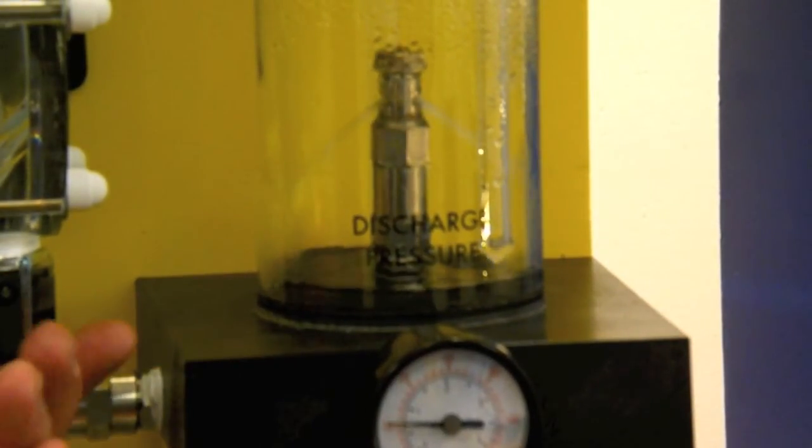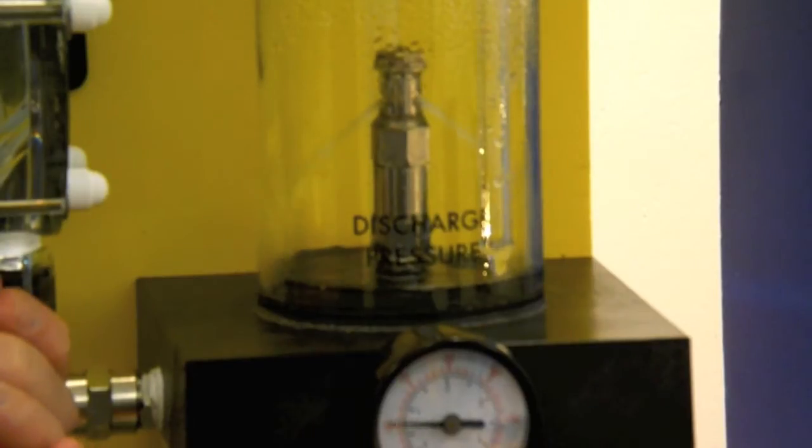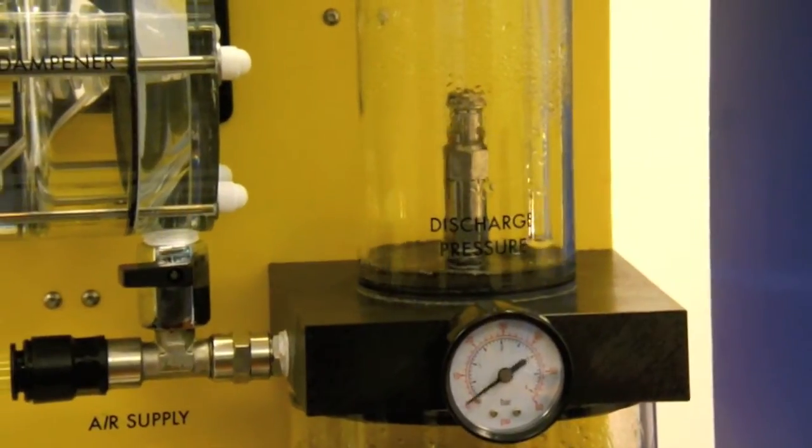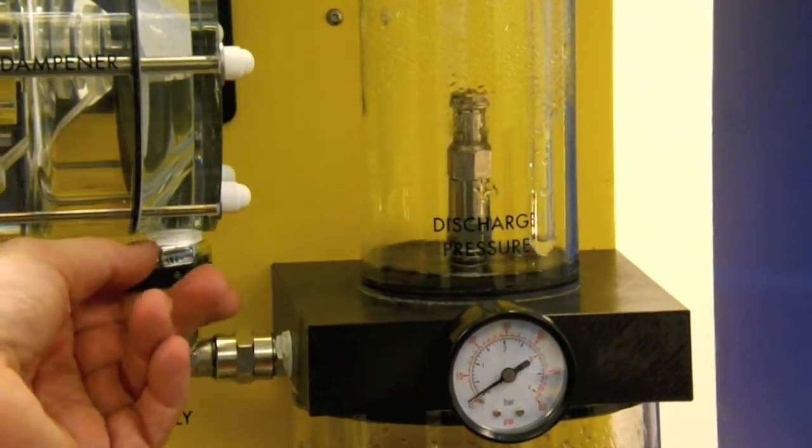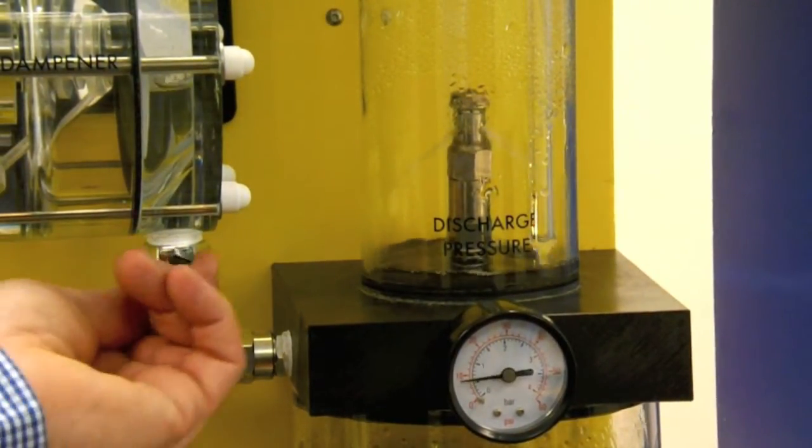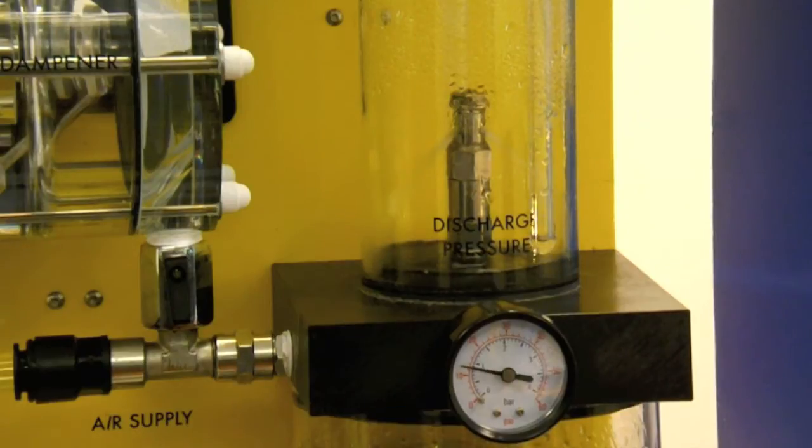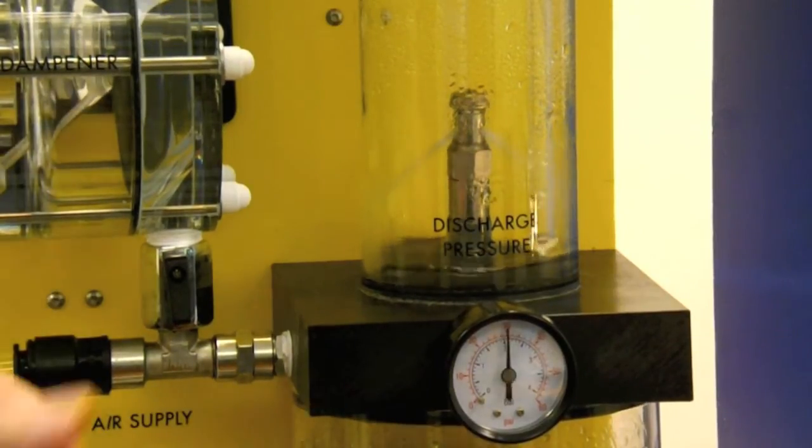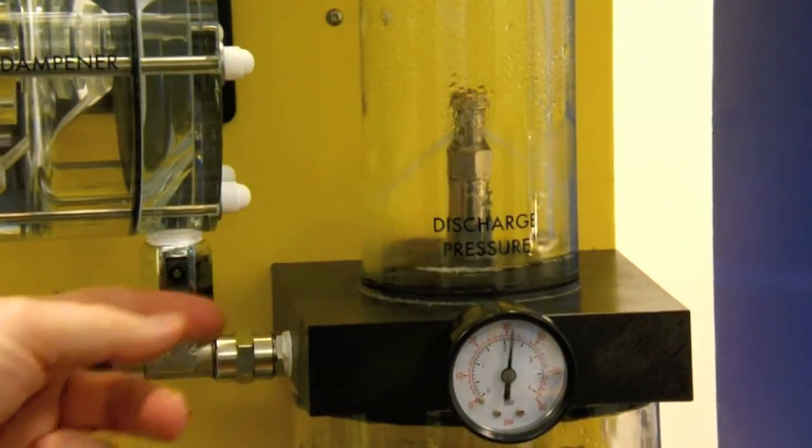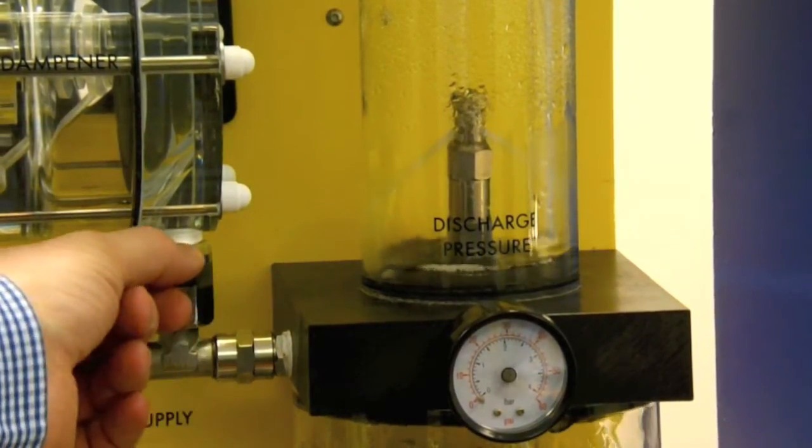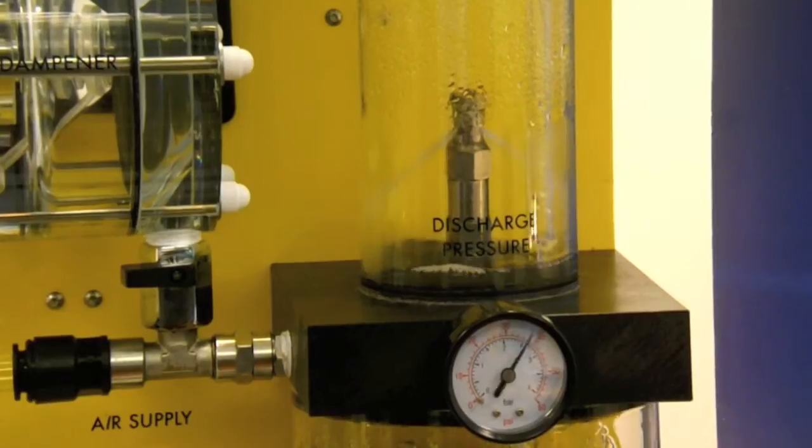So if I close the valve and isolate the damper you will see our pulsation comes back. And if I open up the valve and put the damper back on line our pulse disappears. And this is the same even if we have the pump running quicker. You can see with the pulsation damper on we have a nice smooth flow. With the damper off we have our pulsation back in it.